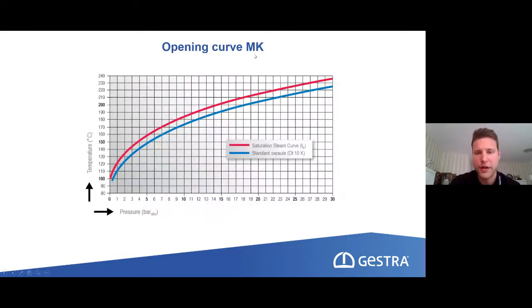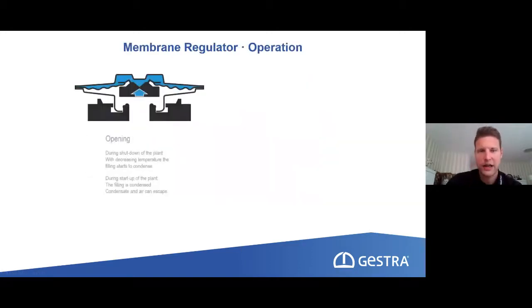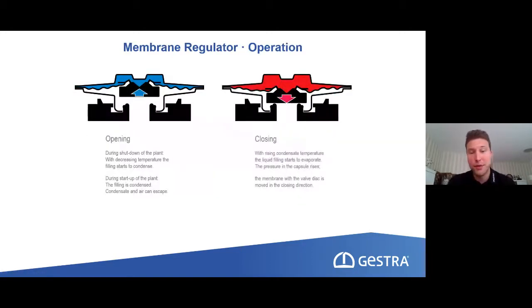So this is the opening curve of the MK. It has on average 10 Kelvin subcooling compared to the bimetallic one, which had 20 Kelvin. So it's closer to the saturated steam curve, which makes it open and close more often. So it will not have this much banking up. The banking up is much less, but we still have it a little bit, but it's okay because we need this banking up of condensate. With this banking up of condensate, we can guarantee that the steam cannot travel through it. So it's always above the water line, which is then the guarantee for not having a loss of live steam. And how does it work? The design of such a capsule is simple but genius.